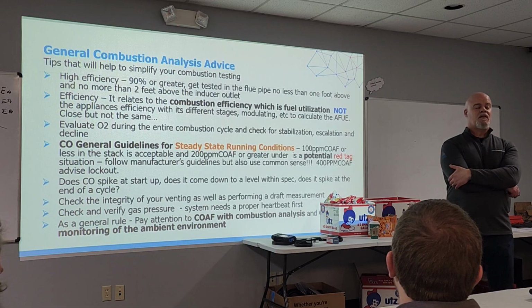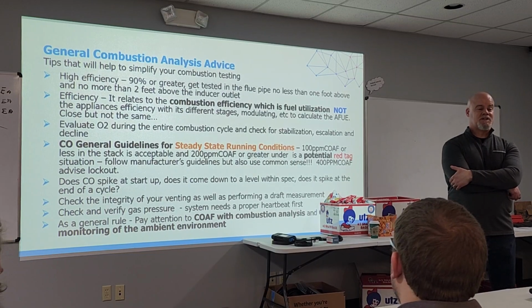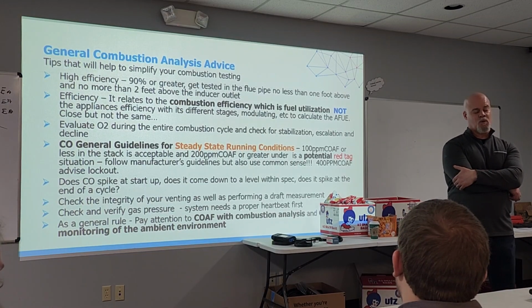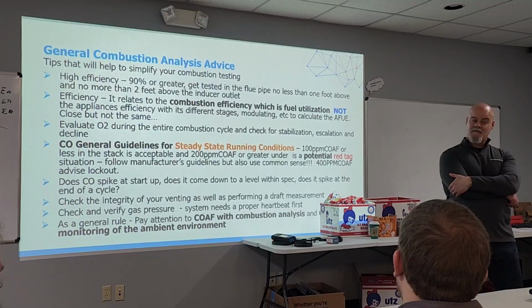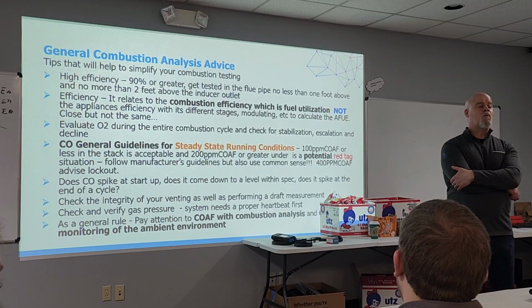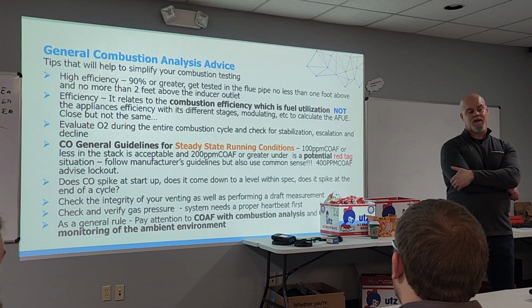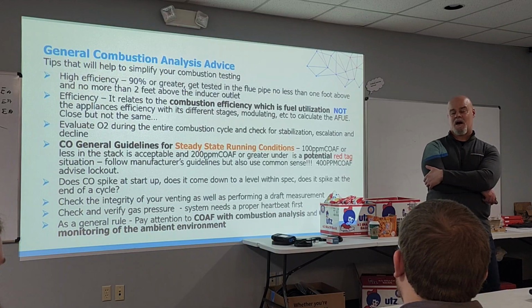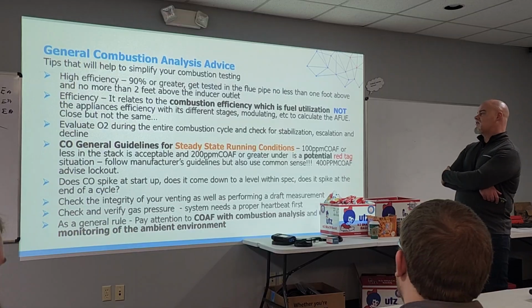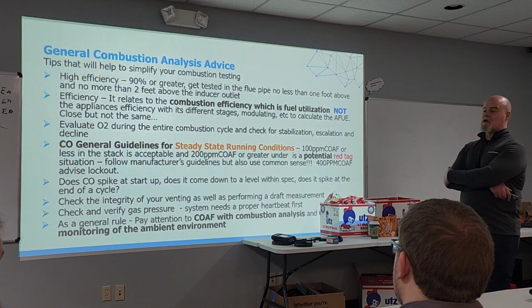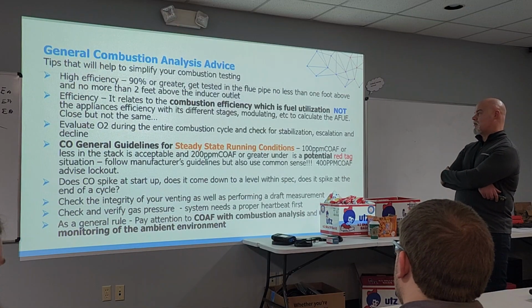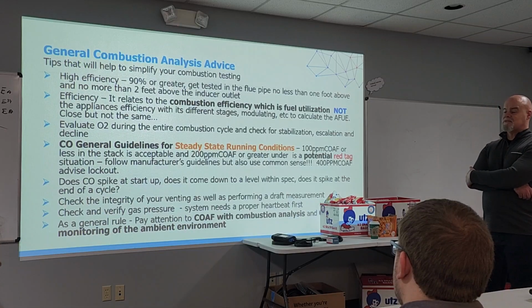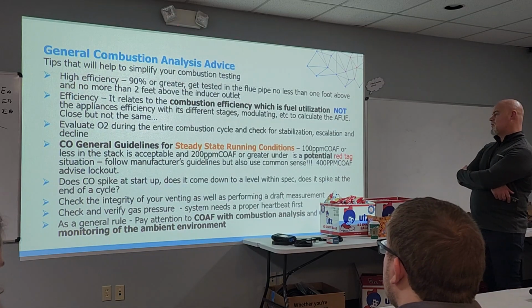Same thing here. The analyzer is giving you the combustion efficiency, the fuel utilization, which is its efficiency number. However, that number will be 1 to 5% off of what the actual AFUE number is, depending on the temperatures outside, depending on the time of year, especially for condensing systems, obviously. So it'll run between 1 and 5%. So it is very, very close, so you can sell off of that, okay? So it's very important to know that difference between the window sticker and the AFUE.